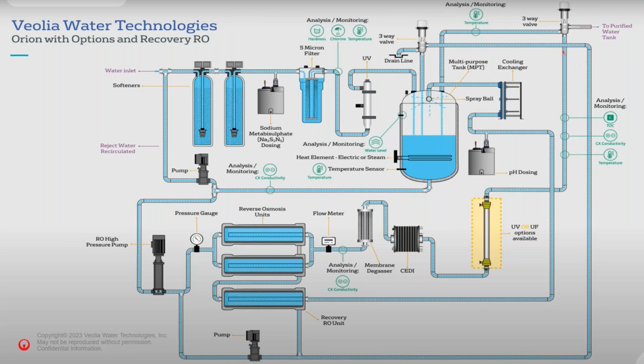to the purified or cold WFI tank at this point here. When that tank is at high level, the water continuously moves because we don't stop the water. We continuously make sure the water moves and is returned back to the multi-purpose tank at this point here. And during recycle, we tend to reduce the amount of water we throw down to the drain. On a typical RO system, the RO pump will induce some heat into the system. So if you're continuously recirculating, you still have to draw off some water to drain and make some fresh water up to maintain the temperature to around 20 or below 20 degrees if you can, because anything above that is a nice environment for microbials to grow.